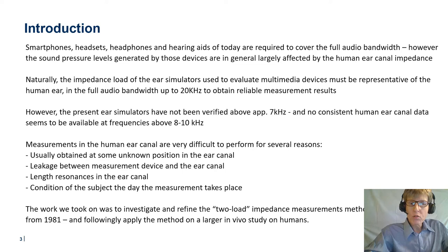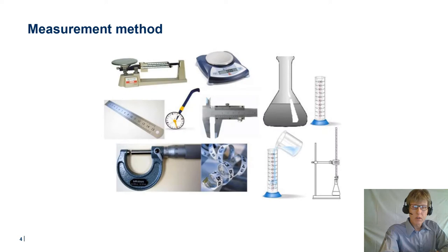The work we took on was to investigate and refine the so-called two-load impedance measurement method introduced by Rabinowitz in 1981, and subsequently apply the method on a larger in vivo study on humans. The two-load method is based on measurements in two known reference load cavities, thereby estimating the Thévenin equivalent of a transducer source or the input impedance of an unknown load connected to the source.